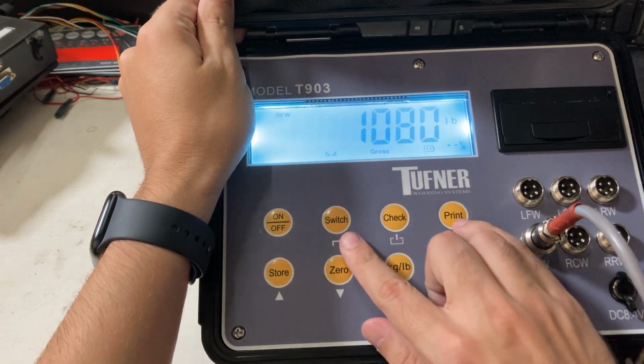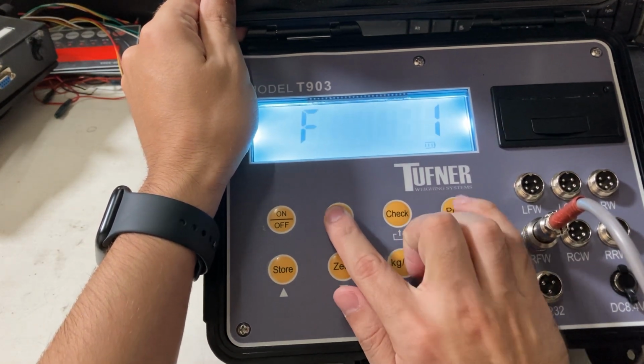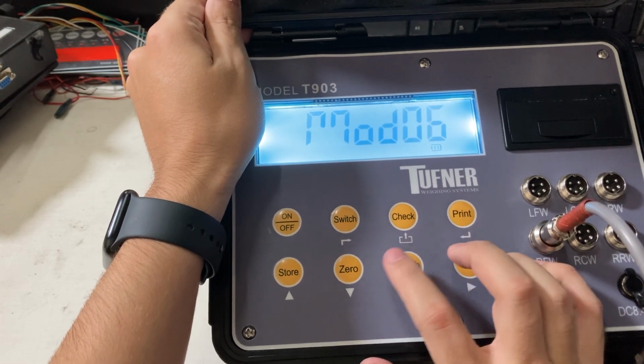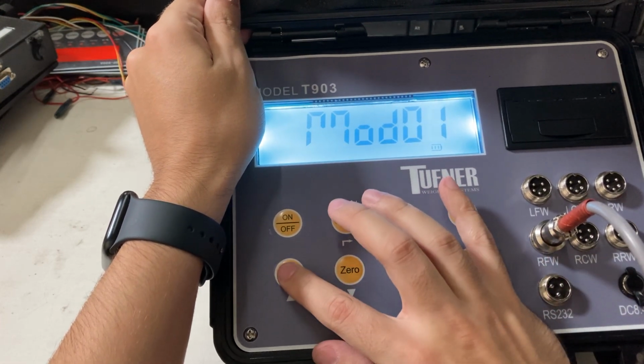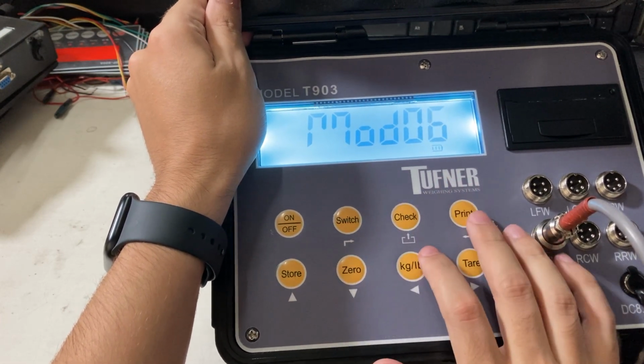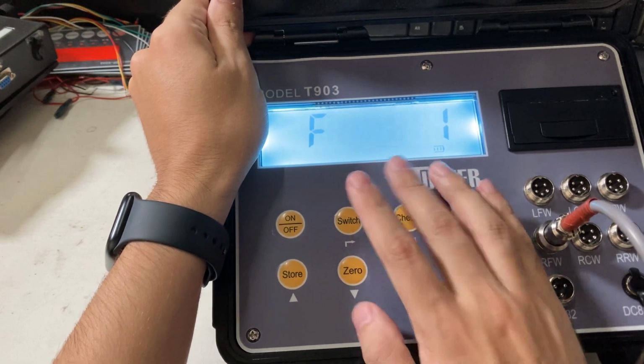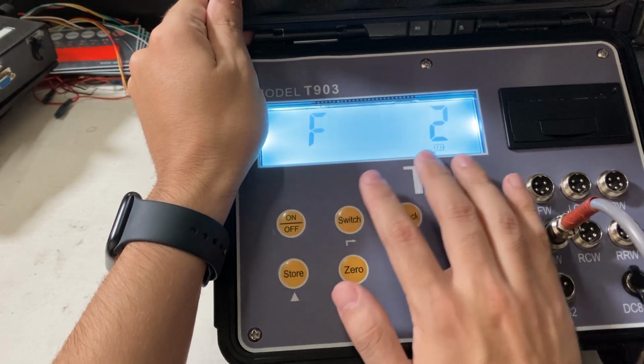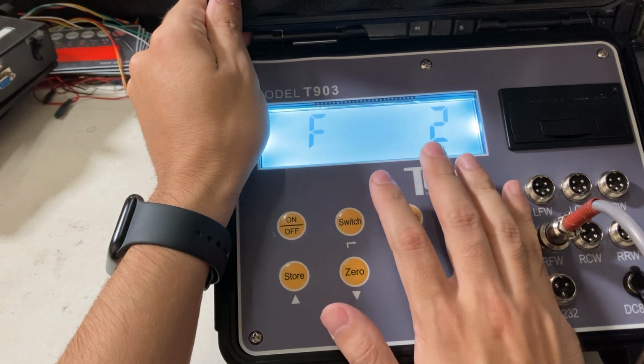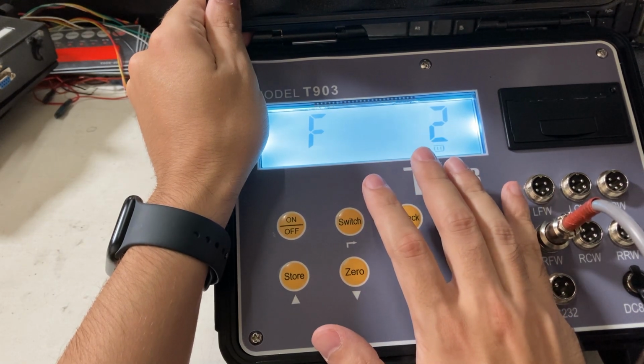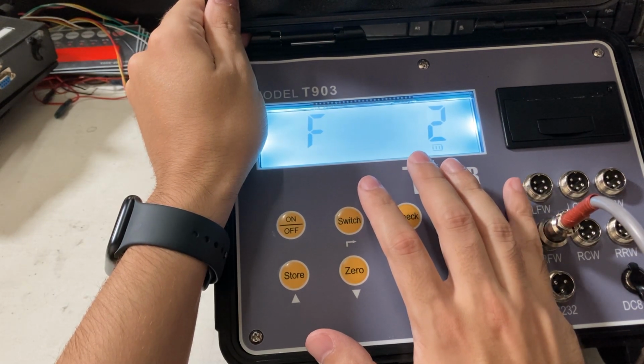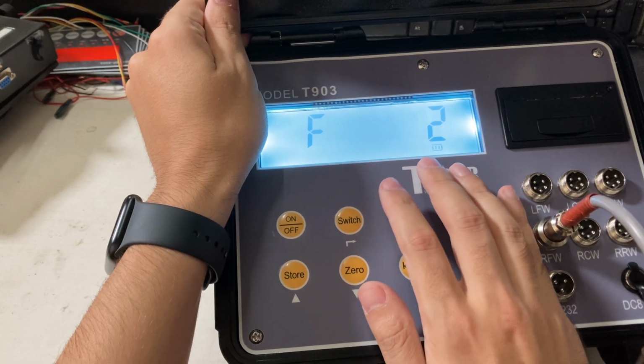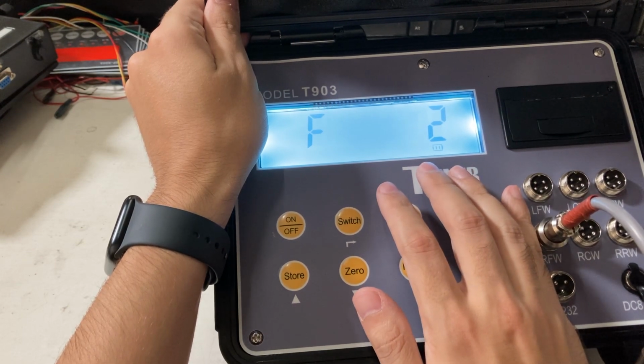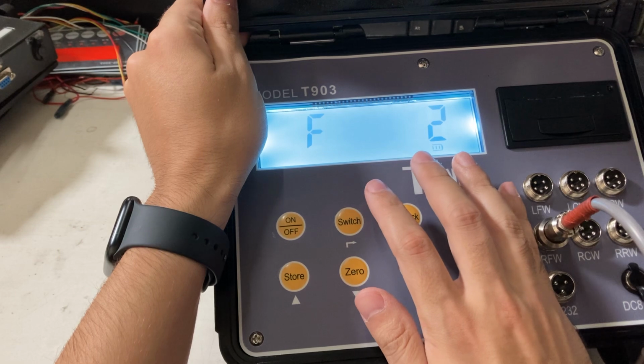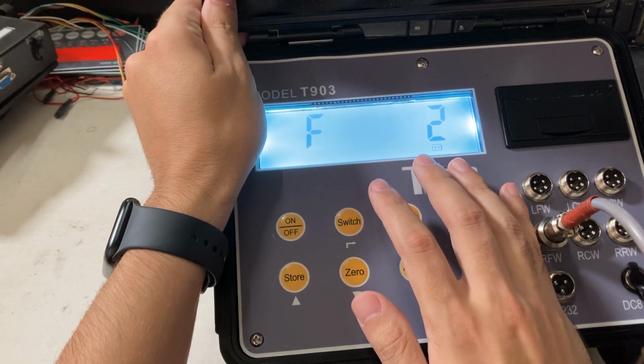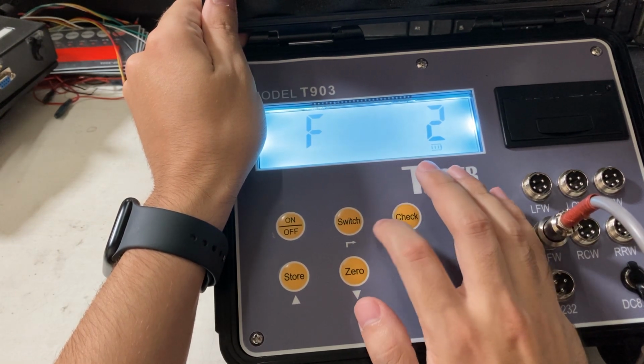So if you're in the process and trying to add more pads, you'll check your F1 setting and adjust accordingly to how many pads you want to have. Correct. And then the F2 setting will actually start setting up the calibration. So you have to calibrate individually. So you plug in and actually put the weight just for that one pad. You can have all of them connected at the same time and do this calibration, or you could just do in pairs. At least do in pairs recommended, because it might throw off the calibration of another one.